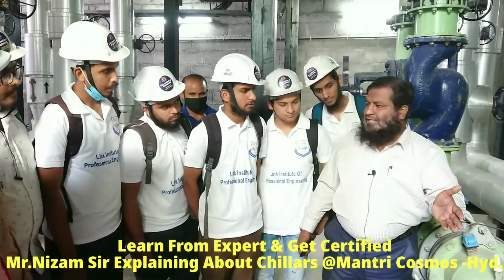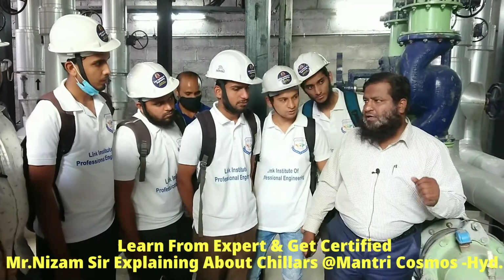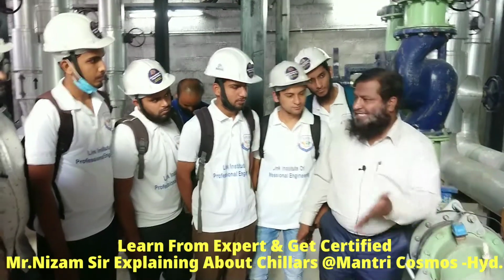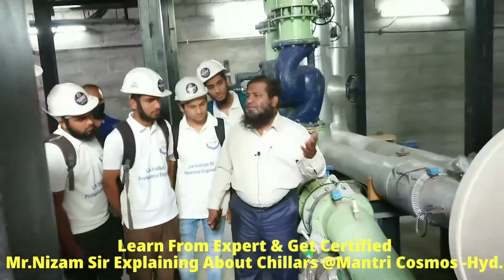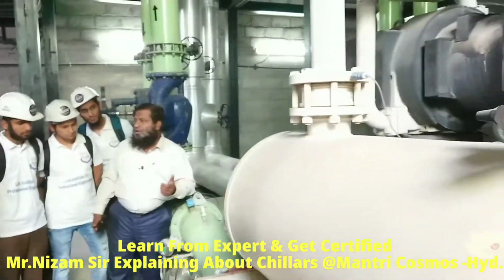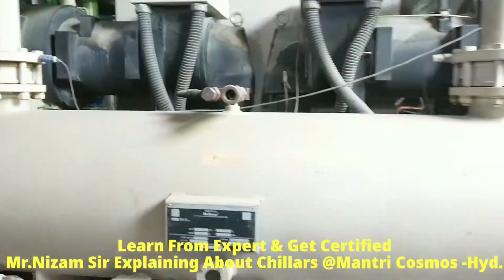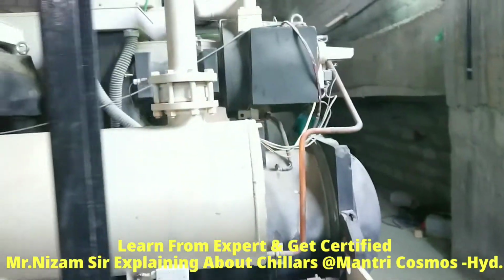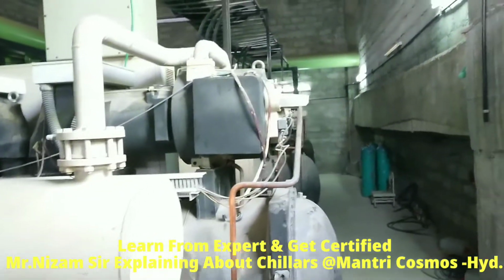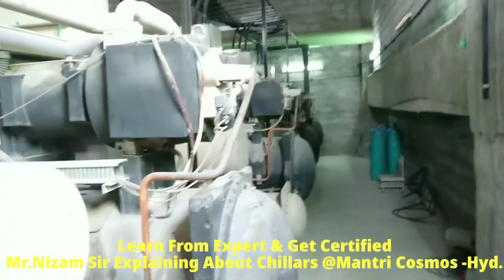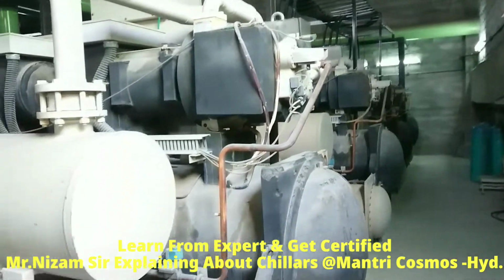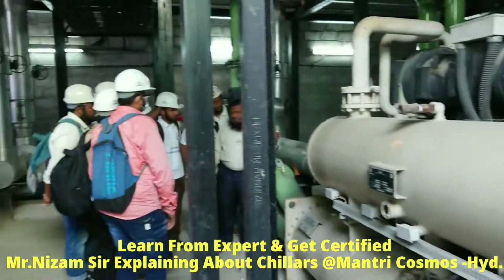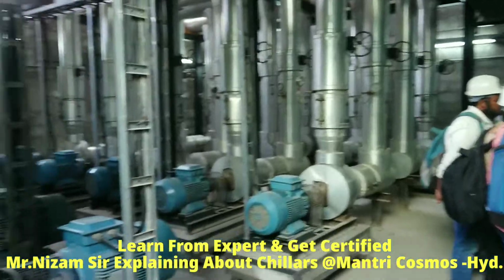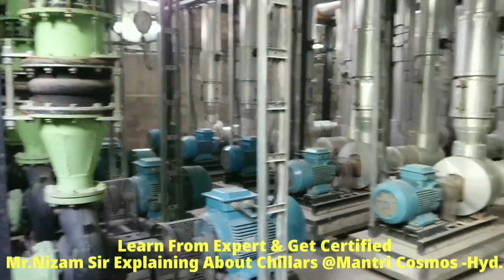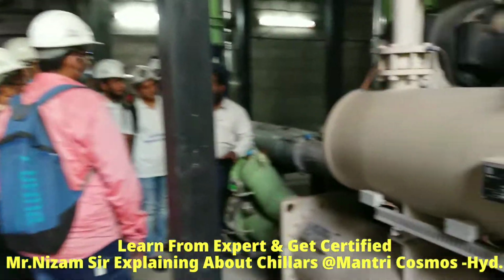This condenser is basically a shell and tube type of heat exchanger, where the shell is an outer casing and the tubes are inside, where the refrigerant is inside the tubes. Or sometimes we have water, depending upon the manufacturing type or the type of condenser we are using. So the high pressure, high temperature superheated refrigerant, after getting compressed in the compressor, which is a screw type compressor, comes to the condenser, where condensation happens.